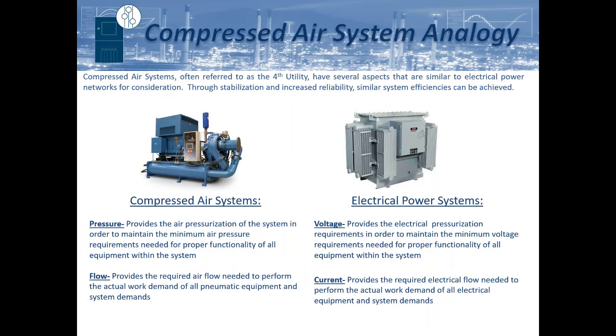So in looking at just a typical compressed air analogy, for those that are not as versed in the electronics world, it's an easy analogy to share with people: how an electrical system compares with a compressed air system. With a compressed air system, you have pressure and you have flow. The pressure is what's required by all the components within that network to perform as designed, and the flow is actually what's providing the work. The same holds true with voltage and current. The voltage is the pressure, the electrical pressurization on that network, and the current is what provides the electrical work.